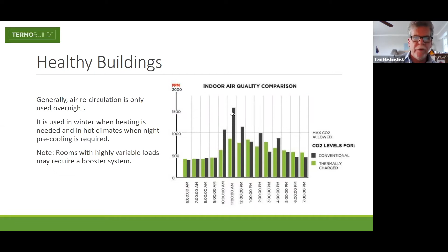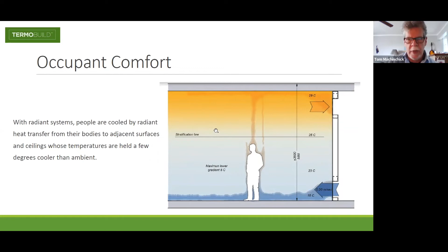So one of the reasons why a radiant air conditioning and heating building is comfortable is that people are cooled by the radiant heat transfer from their bodies to adjacent surfaces whose temperatures are held a few degrees cooler than ambient. So the input air comes in low. Actually, I want to go to the next graph. This is a better illustration of it. Warm air has buoyancy, and it allows the air to transport itself higher. So you put the treated air where it comes in low, where the people are located closer to the floor, and you allow the stale air to drift higher and be exited from the room or the space that's being conditioned. With a forced air system, you see that the air comes in high and exits high, as an example.